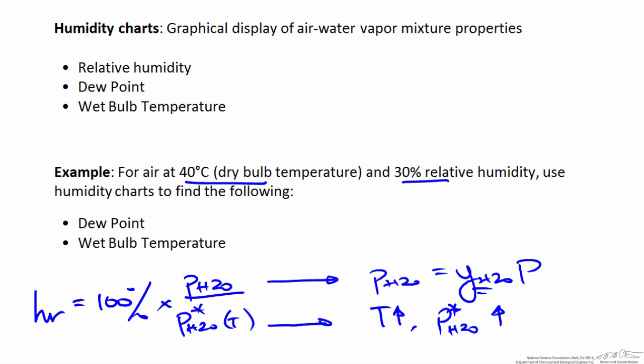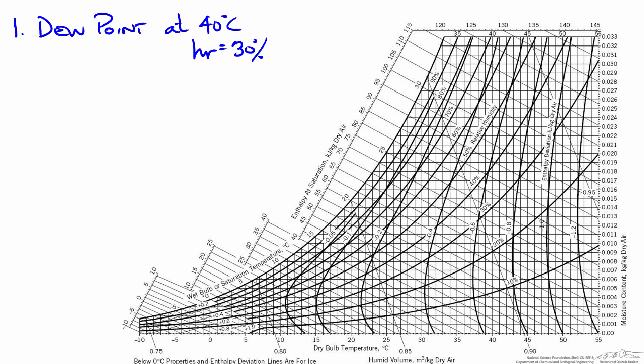First we'll tackle the dew point. We'll go straight to the humidity chart to find where we are and how we find the dew point. The dry bulb temperature is found on the x-axis of the chart — here we know it is 40 degrees. The relative humidity can be found on the sweeping curves across the chart, and here we know our relative humidity is 30%. So if we find the intersection of 40 degrees dry bulb and 30% relative humidity, our air is at that point on the humidity chart.